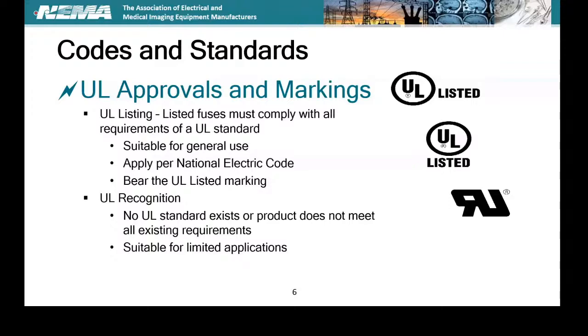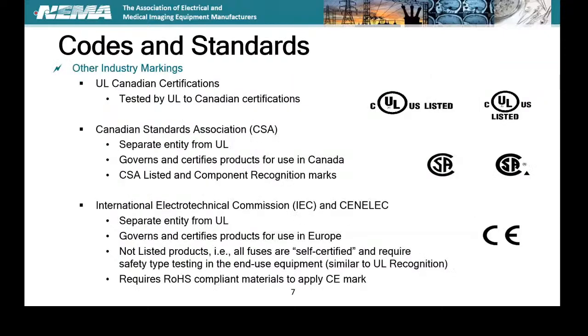Now here is some other markings you want to look for, and here is a dual listing. So we have a Canadian and a UL standard, or list marking, I should say. So the top marking is both listed for Canada and US. The CSA marking on the bottom, another testing laboratory in Canada. And so they're going to do testing for products in Canada.